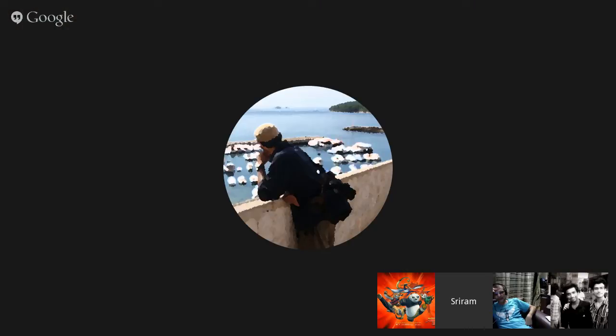Right. I should mention to you, he did something interesting. So generally with these sensor systems, we have only one sensor in each sensor package. What he's done is he's looked at multiple sensors within a sensor package. That way you can do an averaging, a local averaging as well across, say, 2 or 3 sensors within each package. The idea being that if sensors fail in the field, then you can just reroute and swap to a different sensor. Exactly. So maintenance becomes easier. The cost of these sensors is quite low, so you can throw more sensors into a package and not have the BOM go up too much. Exactly. So it's like a hyper-local calibration, hyper-local averaging, and then obviously it flows down the network in terms of the calibration factor.